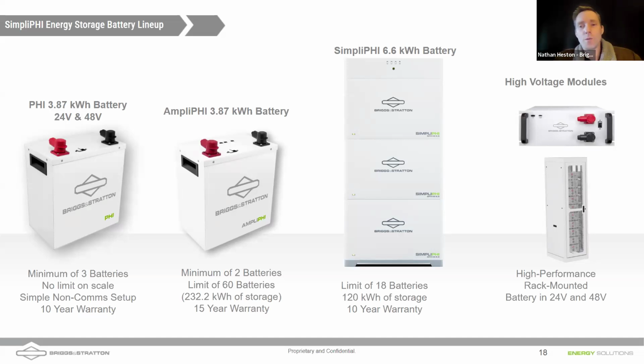What's on the right side? What are we looking at? The right side is one of our high voltage modules. So unlike the batteries on the left side, which we all run in parallel, we can run these batteries in series to build up that DC voltage, which allows us to run more commercial applications, such as three-phase 208 or three-phase 480 systems as well.